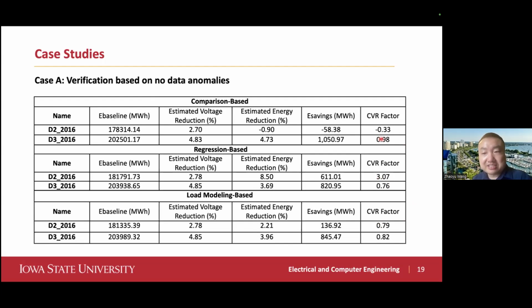For the other data set, D3, we have a much better result. The CVR factor is fairly consistent across all three methods, giving us some confidence that for this feeder, the CVR factor should be around 0.8 to 0.9.